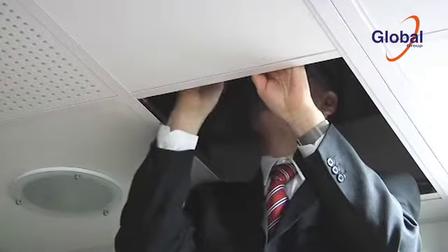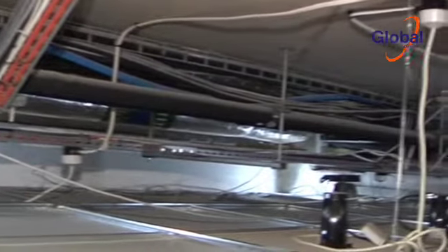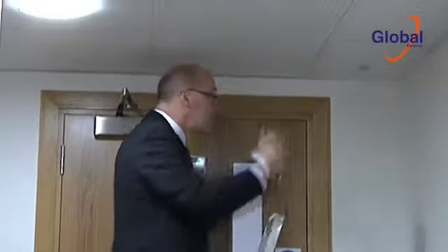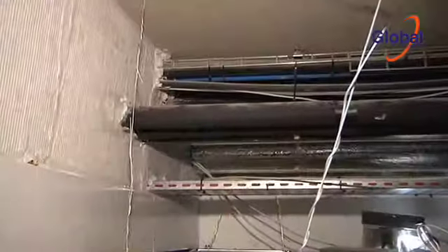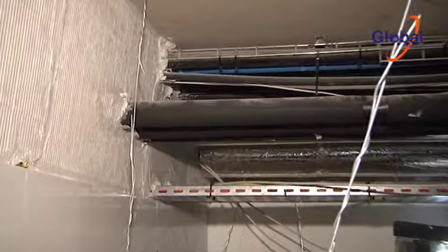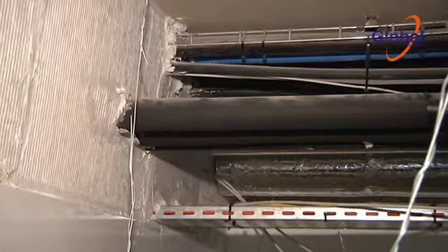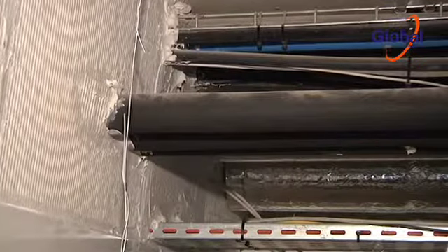Suspended ceiling voids, especially at corridor ends, should be inspected to determine the condition of the fire-resisting construction above. Particular attention should be paid at fire door positions to confirm walls above suspended ceilings extend fully to the floor slab above. All services that penetrate walls, ceilings or floors should be checked to ensure that they are suitably fire-stopped, especially if any recent work has been performed.